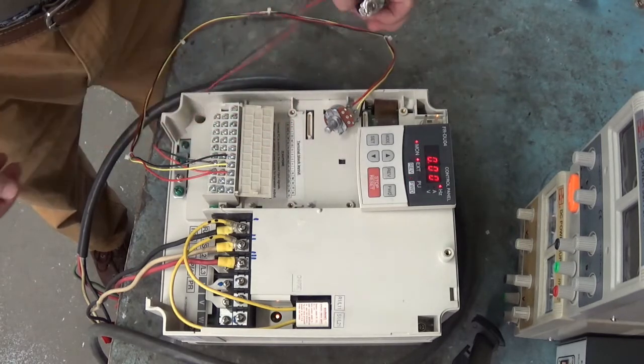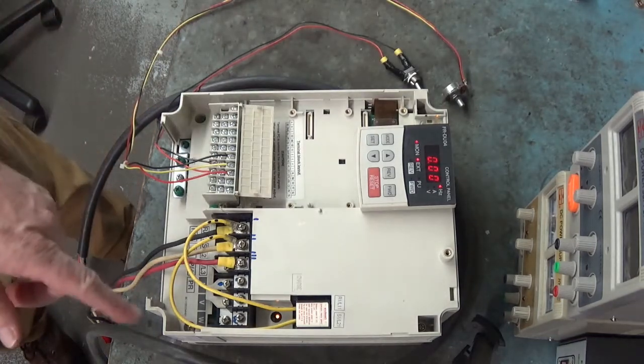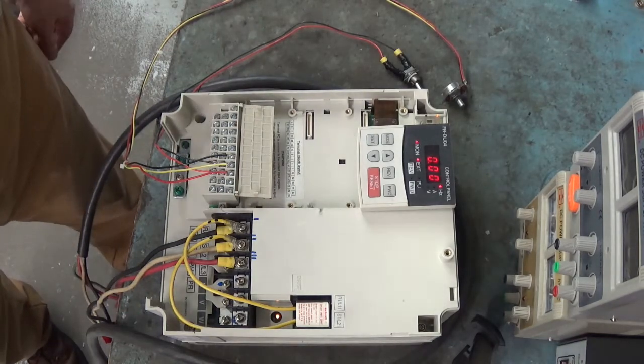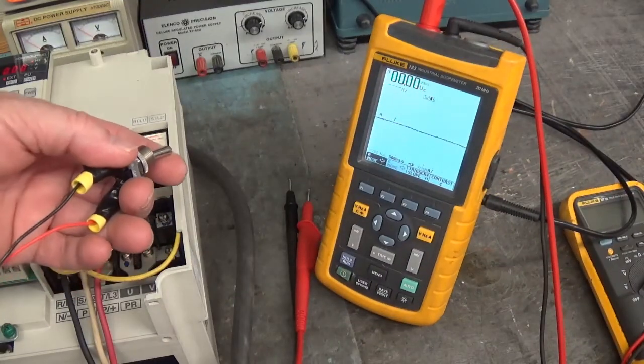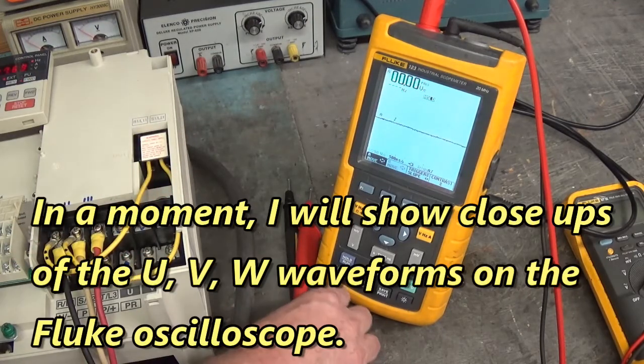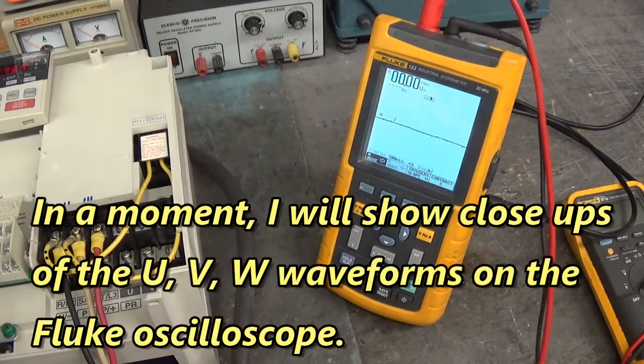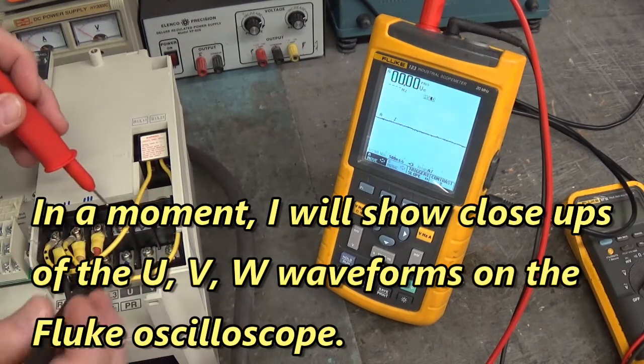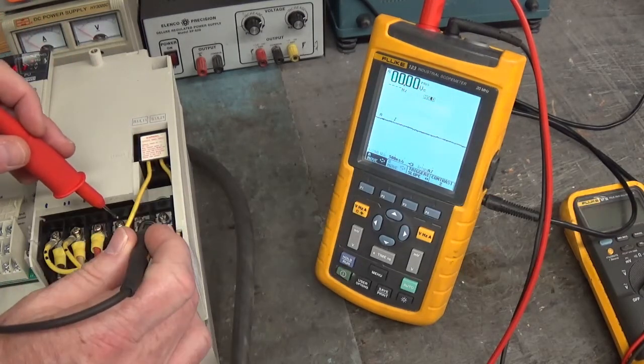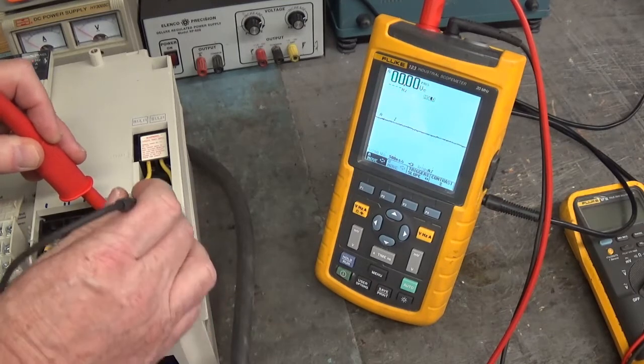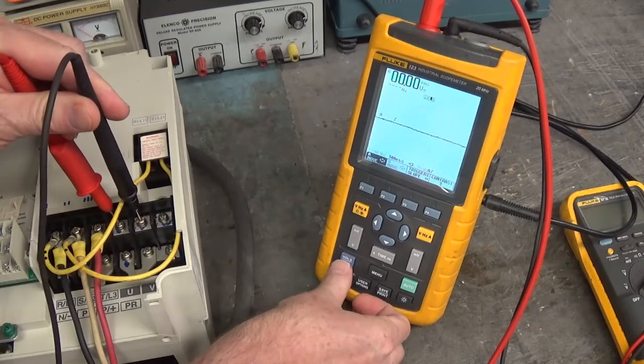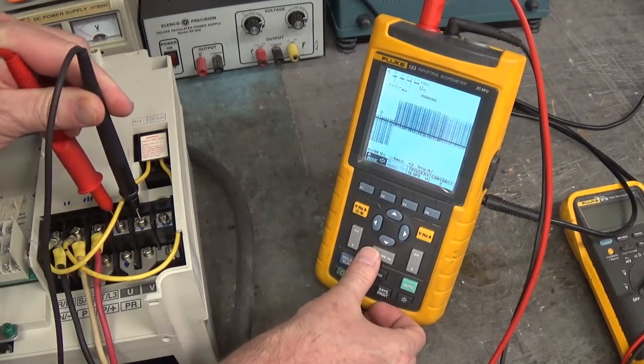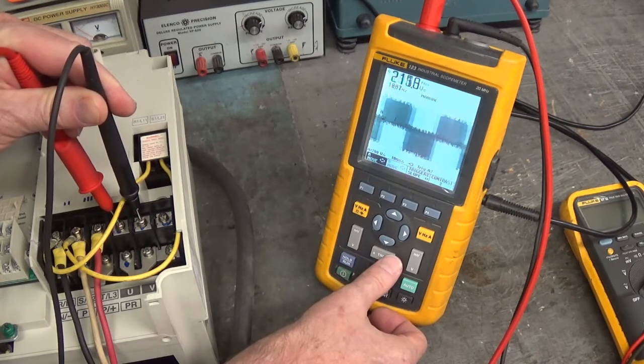Let me go drag the oscilloscope over here. We'll look at U, V, W, see what it looks like. All right. Enable the drive to run. We have our 17.6 hertz on the display. We're going to look at U, V, W. Here's U to V. That looks good.